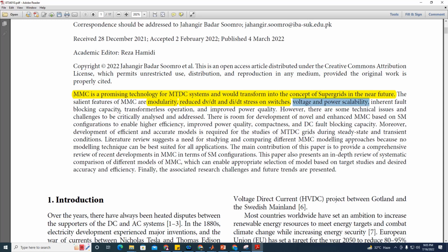MMC can block converter faults, including a very serious and critical fault such as a DC pole-to-pole short circuit fault. This fault is considered very dangerous and critical in the field of MMC HVDC, when the two DC links are short circuited.